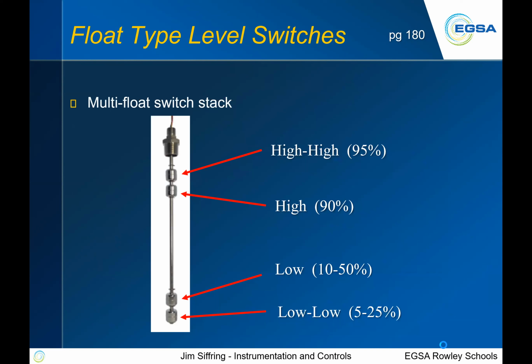But where they're used is in devices such as this, like a multi-float stack switch or single switch stack. You'll see the floats that are on that shaft, and they're limited to how far they can float, but they can set those in all kinds of different areas. You can order these as you see here, or you can custom make them yourself. There's a bunch of float switches. Inside those little floats is a magnet, and inside the stainless steel rod that goes down through all of them are a bunch of those little reed switches. So as the float rises, that magnet will come in contact with the reed switch itself, change the state, and give you some kind of an output.